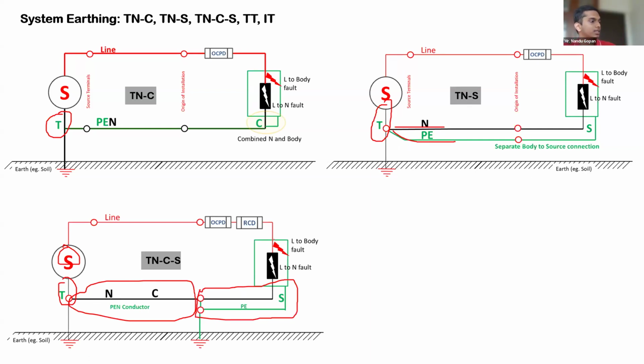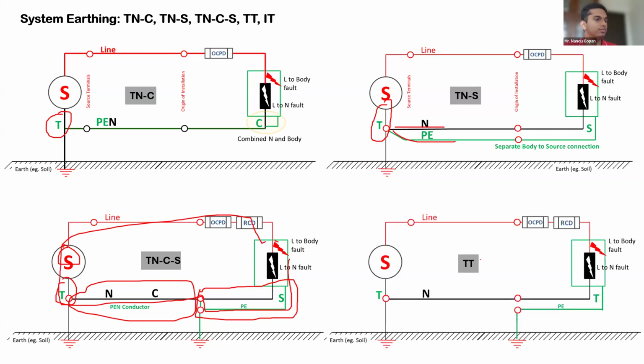So in this case, if there is any earth fault, the fault current will be traveling like this. Next is TT source. TT source is where the system referencing is done here. Neutral and earth have been connected and earthed, and the body of the installation's MET also will be connected to earth. So this is what the TT system is.